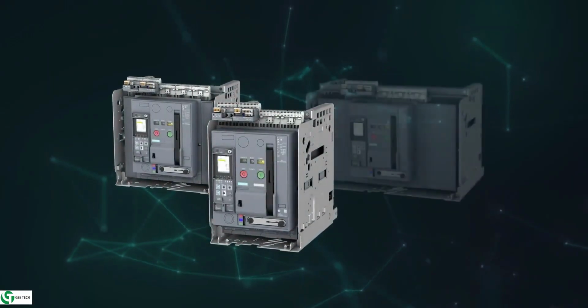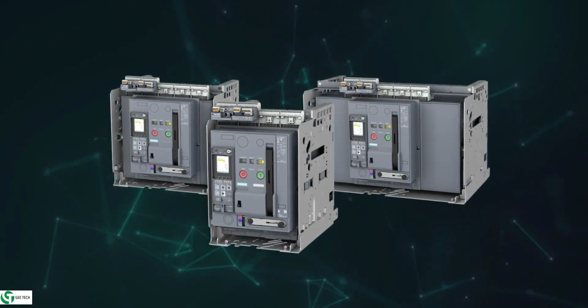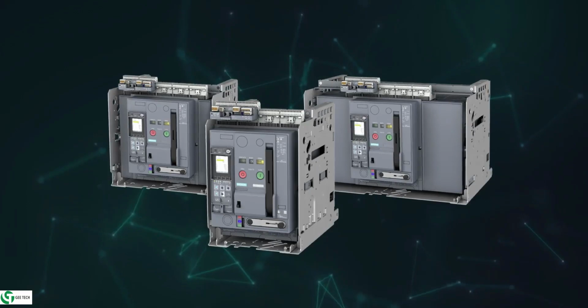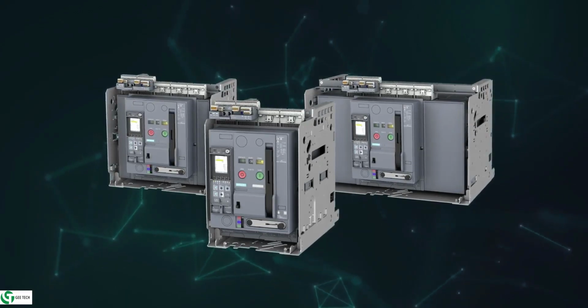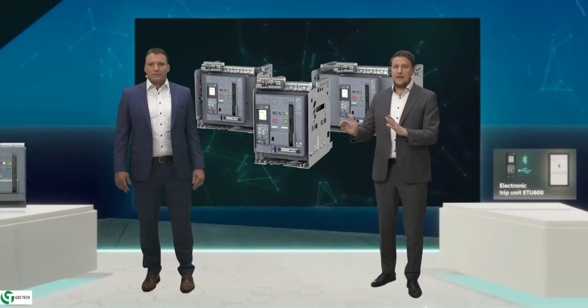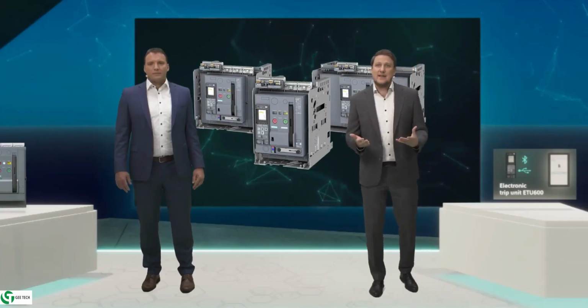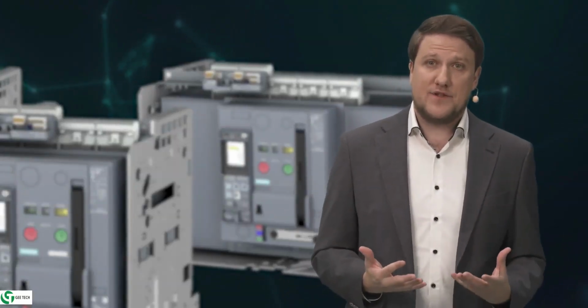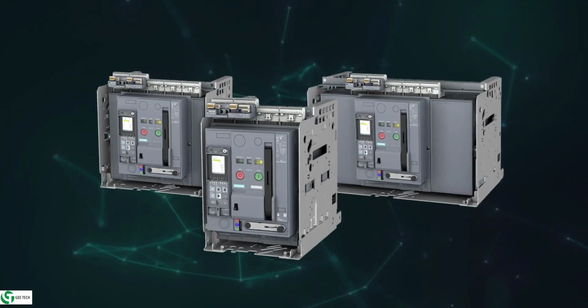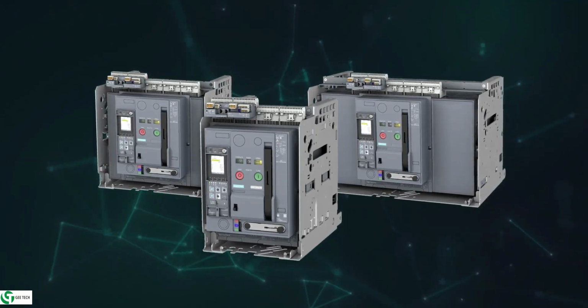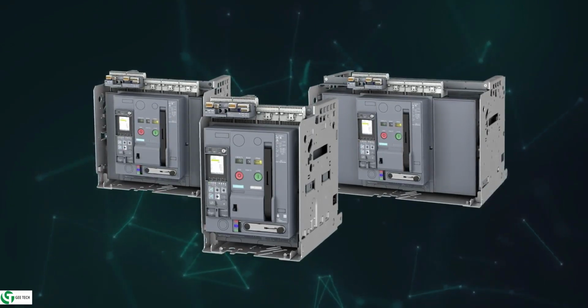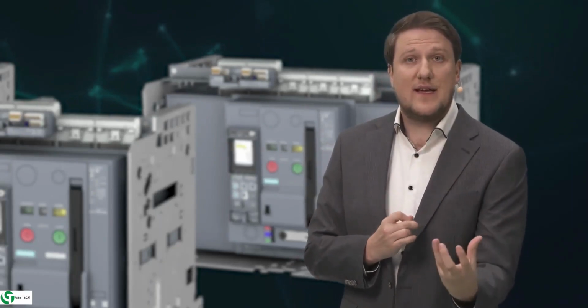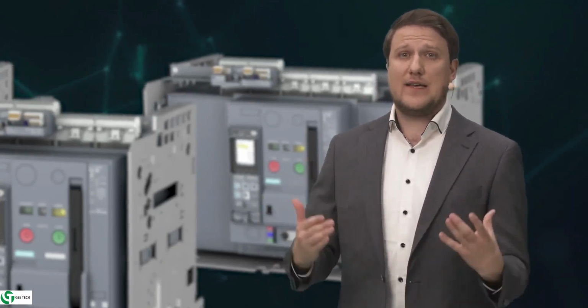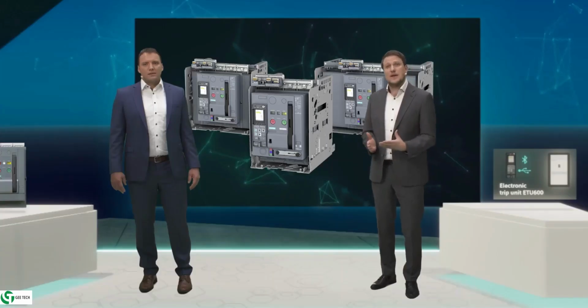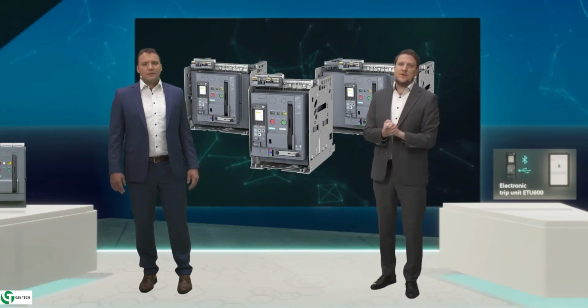Let's have a look at the frame sizes. We are providing three physical different frame sizes of the ACB. This starts with our standard portfolio up to 690 volt application, ranging from breaking capacities from 55 kA up to 150 kA. Then there is additionally one E-class that really satisfies demanding applications or requirements up to 1000 volt or 1150 volt. These breakers really show the highest performance on the market. Speaking about the life cycle value of this product, we show the highest mechanical and electrical operating cycles on the market, which really gives you value over the whole life cycle of this product.